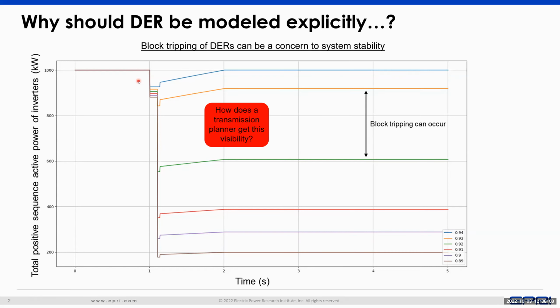DER have this behavior where the moment a fault occurs on the transmission network, a lot of the legacy DER - which have been in the network for close to 15 years now, since around 2003-2005 - were designed under a paradigm that said: if an event occurs on the transmission network, don't try to do anything, just trip and immediately disconnect from the network.